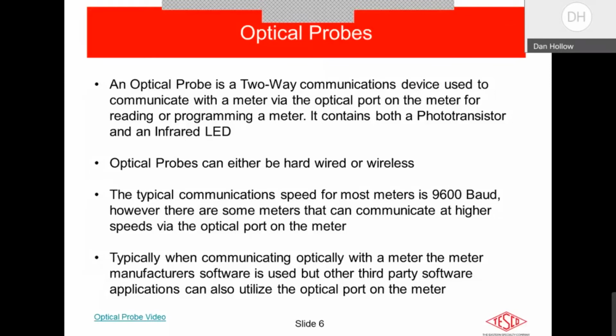There's also third-party software out there. I'm familiar with a package called MVLT, which was multi-vendor laptop. It was a piece of software that started out way back in the early 90s that had the protocols for all the meter manufacturers' meters. So you'd take that universal probe, hook it up to a laptop, and you could go out and probe a GE Aclara meter, a Landis & Gyr meter, Itron meter, Honeywell meter, all with that same probe, all with this one piece of software.